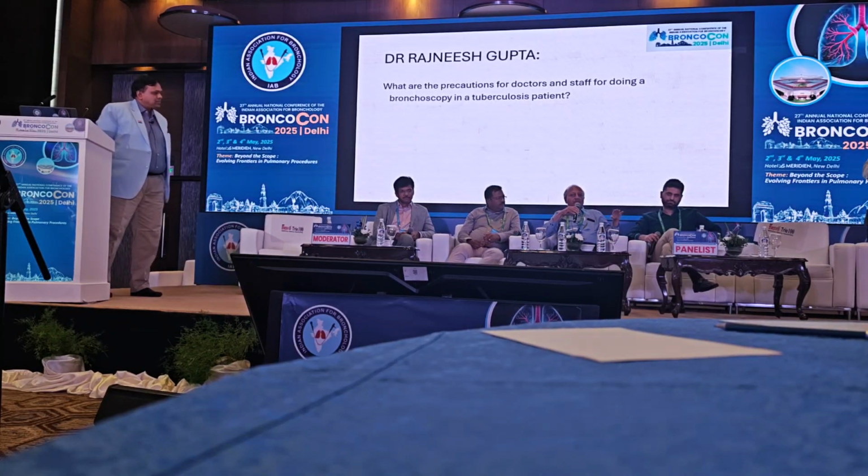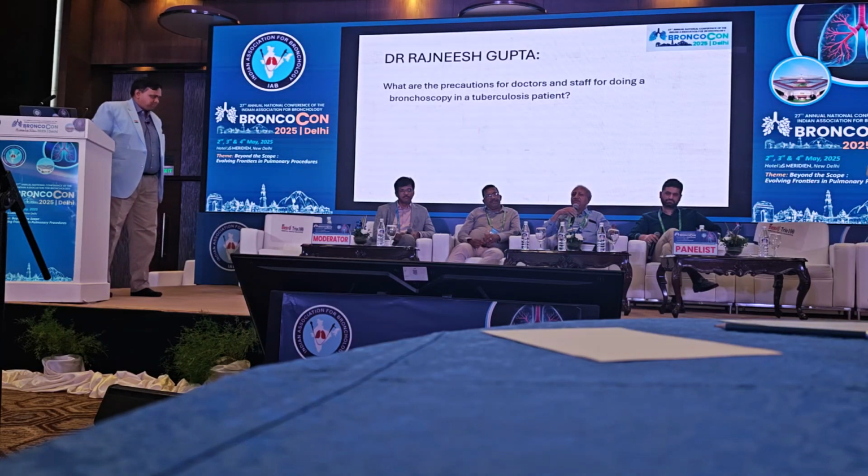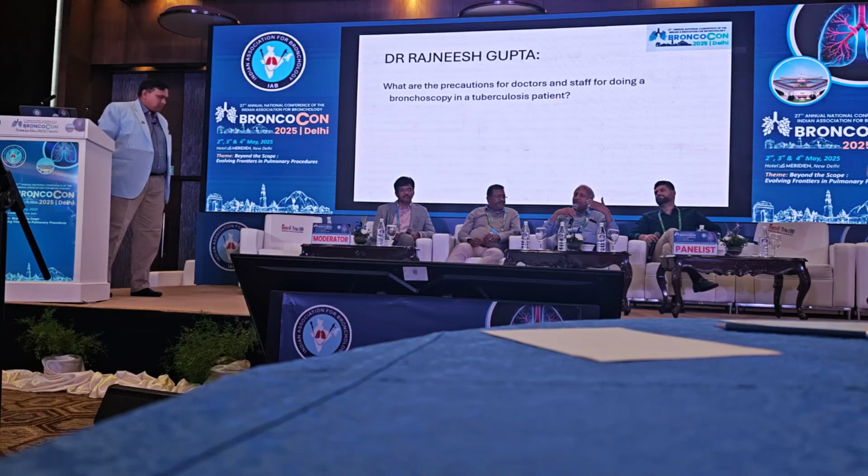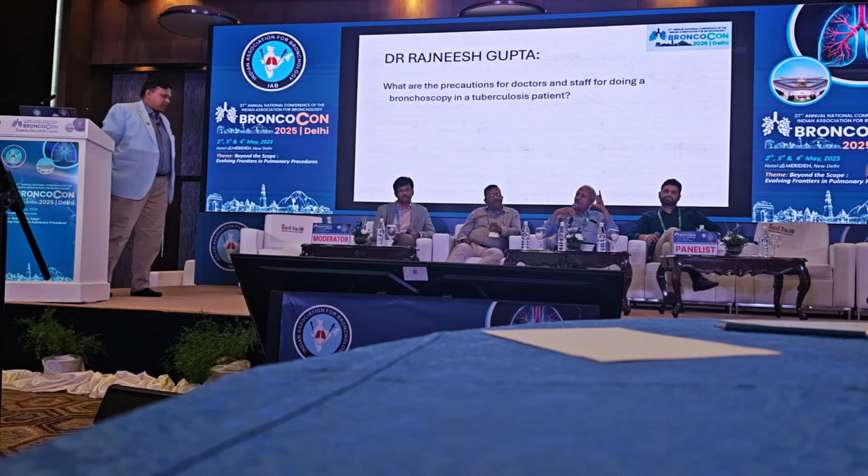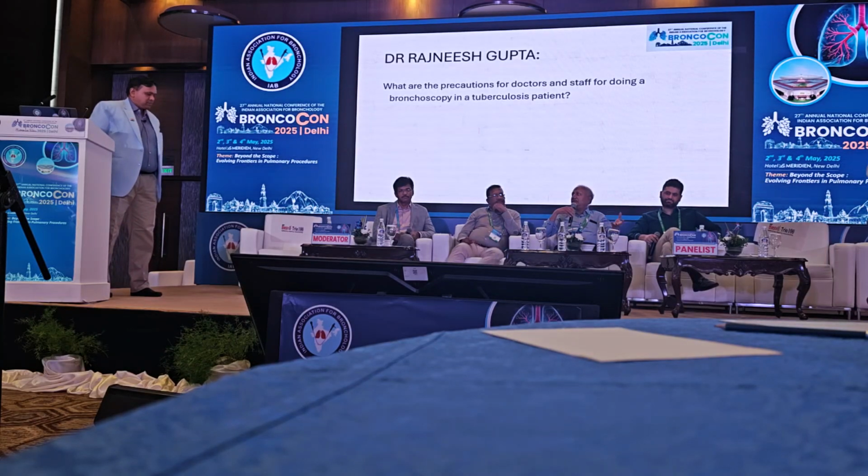Then a negative pressure design should be there. Then a HEPA system should be there. Then a UVGI system, for decontamination of the upper area of the room, should be there. And there should not be any recirculation of air. That automatically decreases the contamination to doctors and staff. Of course, they have to observe standard precautions like the kit, the N95, face shield, and eye shield.